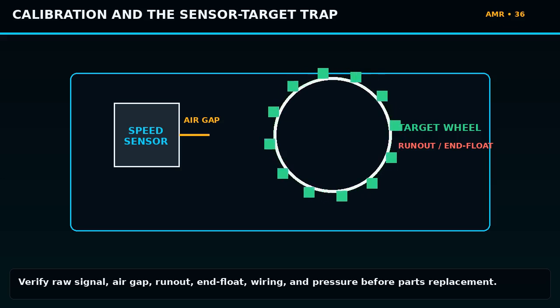First, graph the raw speed signal. Inspect the sensor face and target. Measure air gap and runout to specification. Check connector pin fit and shielding. Then verify clutch pressure and repeat calibration under the correct conditions. Replacing clutches or the controller without proving the signal path can create an expensive repeat failure.